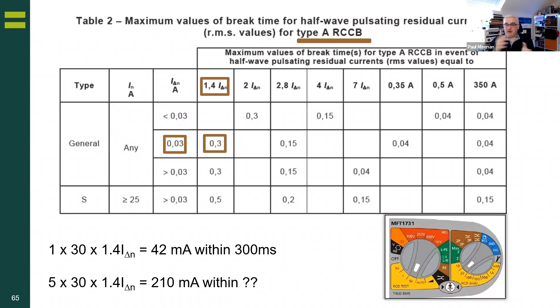However, in my opinion, and it's only my opinion, please follow guidance note 3, because guidance note 3 still tells you to do more tests. And more importantly, manufacturers, every single manufacturer will tell you a different thing. You are required to follow manufacturer's instructions. You may ask your CPS, but they may not have read the manufacturer's instructions. You are the designer, you have the liability, the due diligence sits with you.